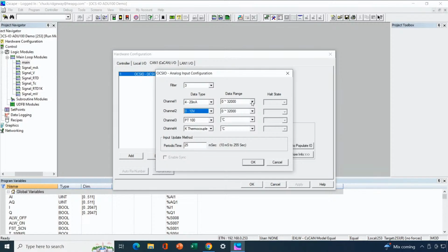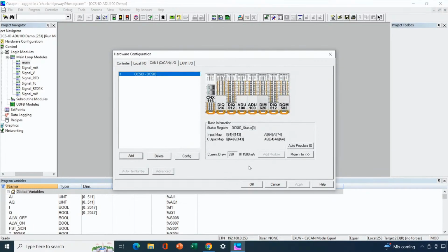Now for voltage, current, and millivolts, you have your choice between a few different ranges. I always select 0 to 32,000. It just gives the most resolution. And then for temperature type sensors, we have our choice between Celsius and Fahrenheit values, and those come back in 10th degree increments. So that's all there is to configuration of the ADU 100.